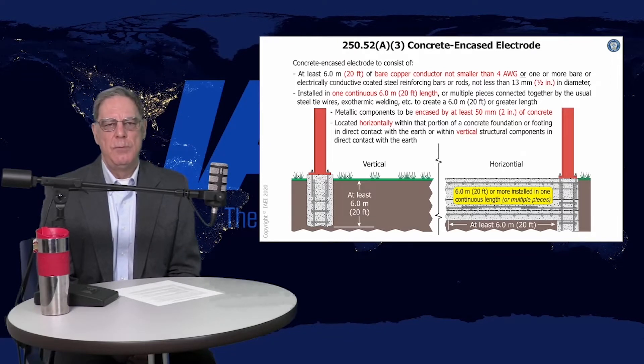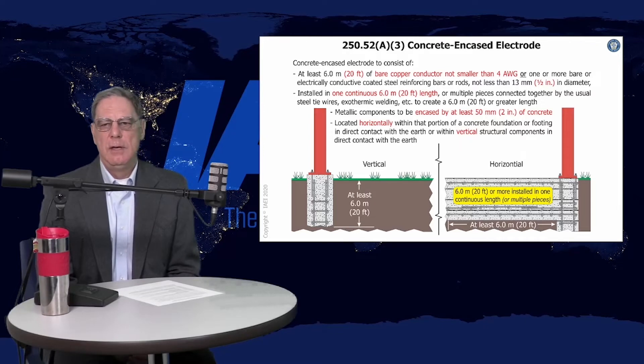The other thing about the rebar is if it's epoxy-coated rebar, that is not conductive. If it's galvanized or bare, then it's perfectly fine in the concrete encasement. The concrete encasement needs to be at least two inches on all sides and can be located horizontally or vertically, so 20 feet horizontally or 20 feet vertically in the concrete.